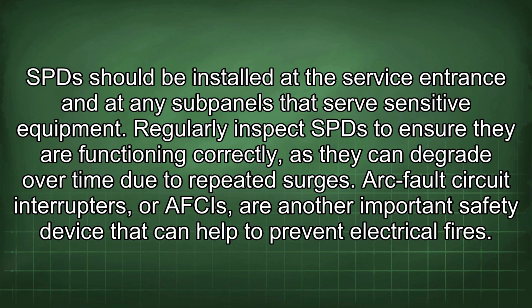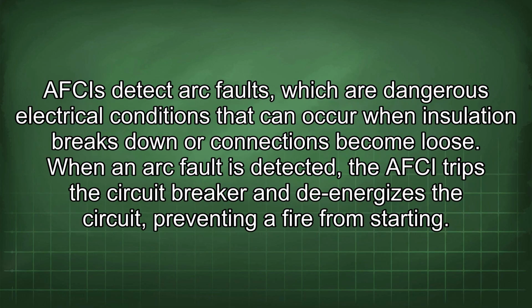SPDs should be installed at the service entrance and at any subpanels that serve sensitive equipment. Regularly inspect SPDs to ensure they are functioning correctly, as they can degrade over time due to repeated surges. Arc fault circuit interrupters, or AFCIs, are another important safety device that can help to prevent electrical fires. AFCIs detect arc faults, which are dangerous electrical conditions that can occur when insulation breaks down or connections become loose.